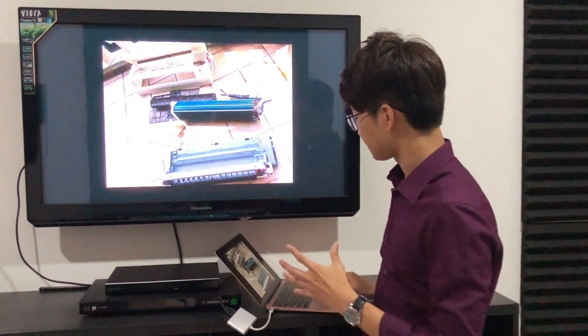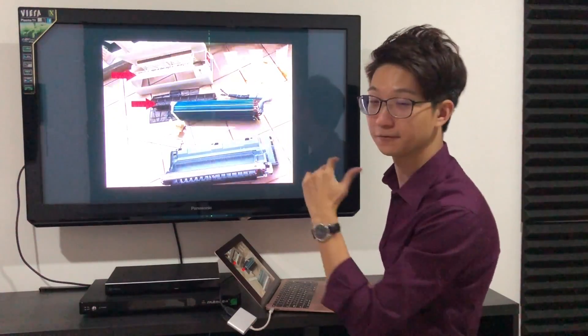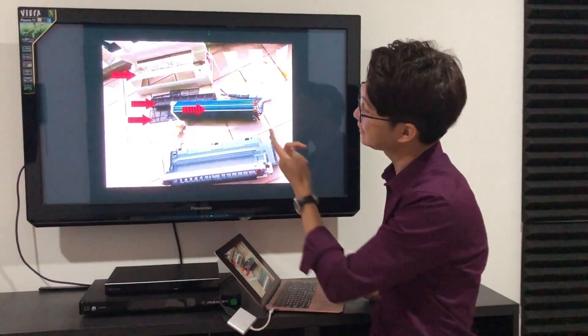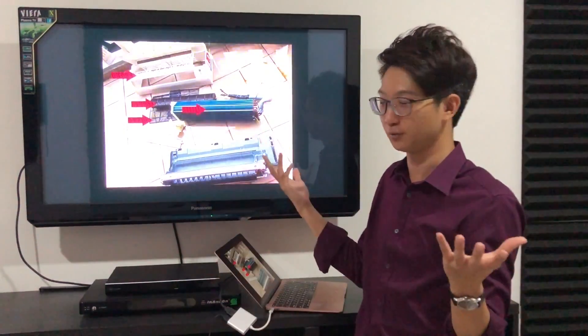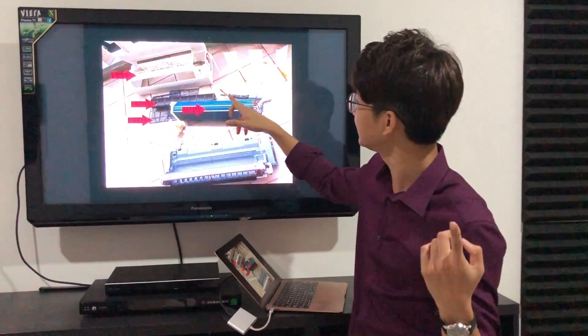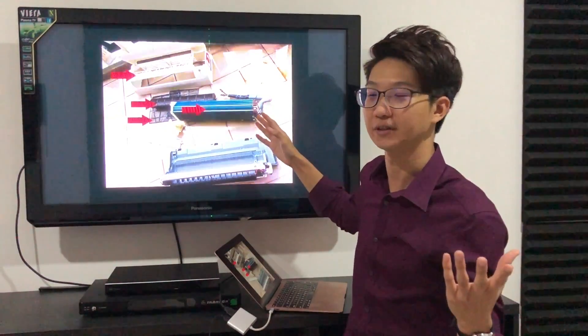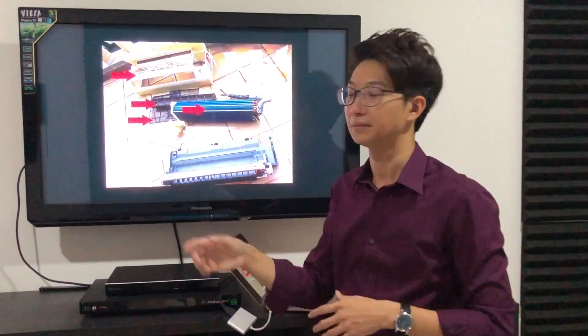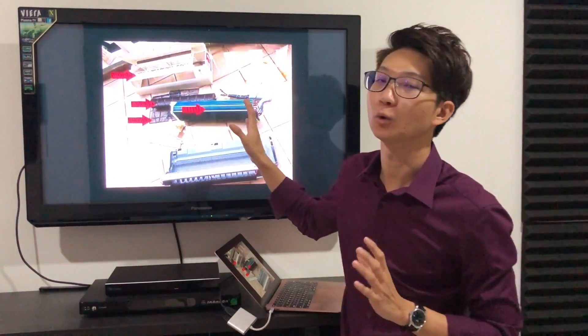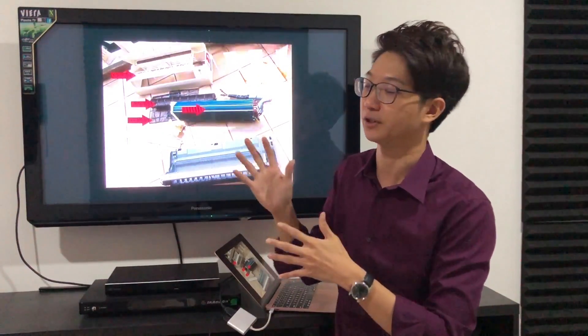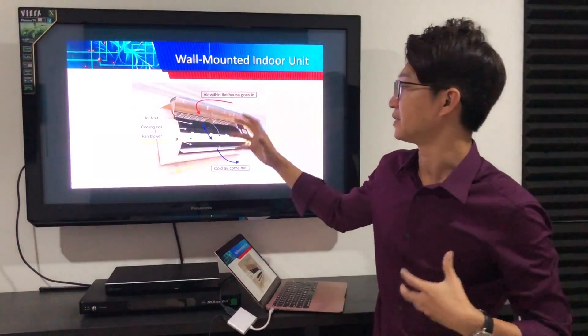If you further dismantle the whole indoor unit, you can see the cover, the fan blower, the plastic filter, and precisely the evaporator — the fin-and-tube heat exchanger. You can see the refrigerant pipe connects here, sending refrigerant into the copper tube. The fins are a blue color because they apply a hydrophilic coating, which improves the anti-corrosion property of the fin. Sometimes older units appear black because they were never coated. This is the basic structure and how it works.